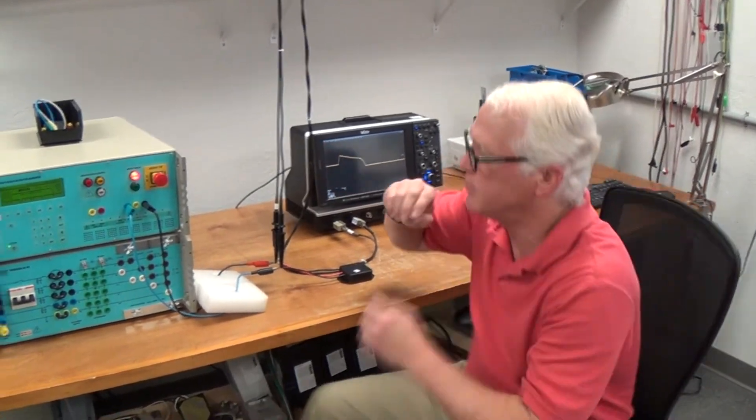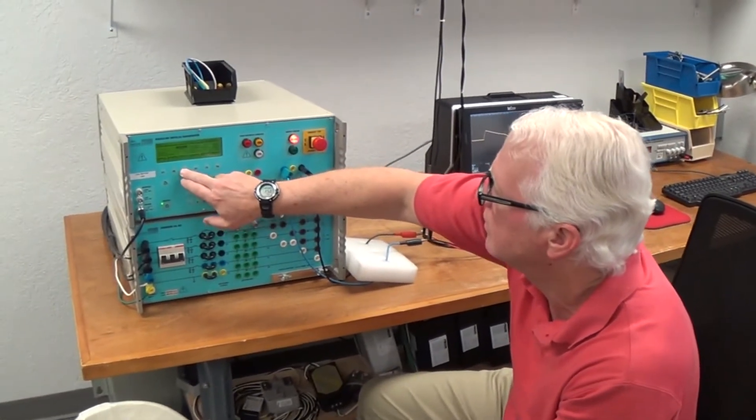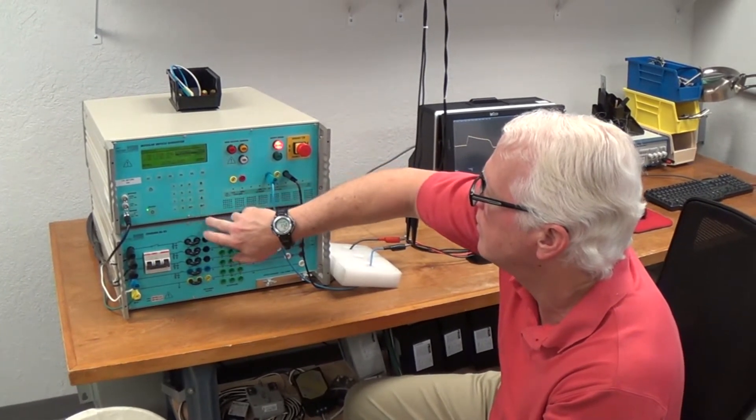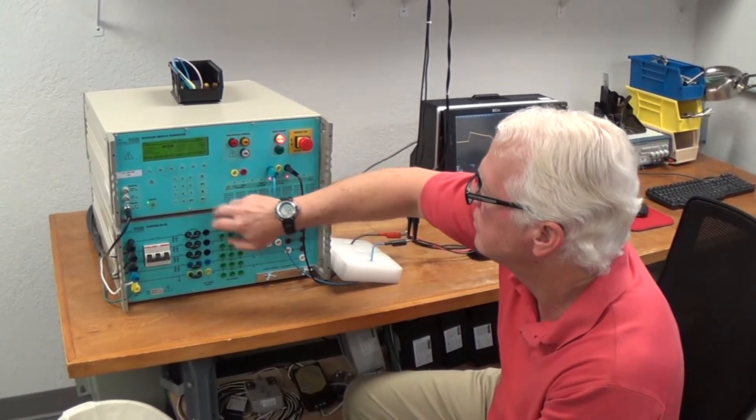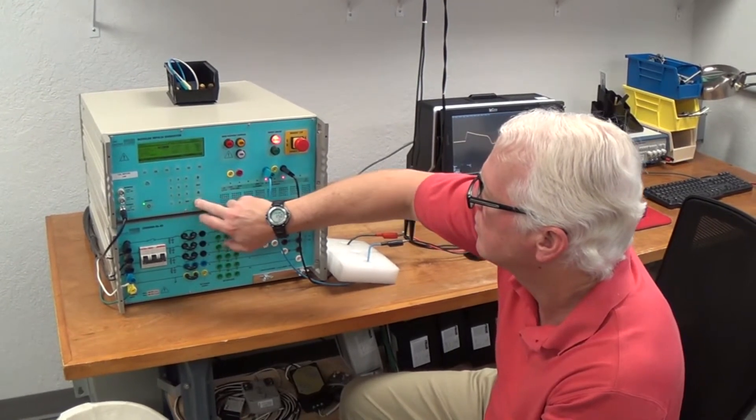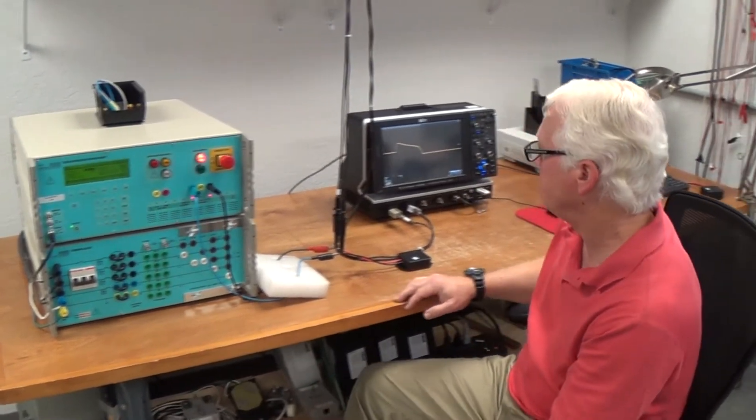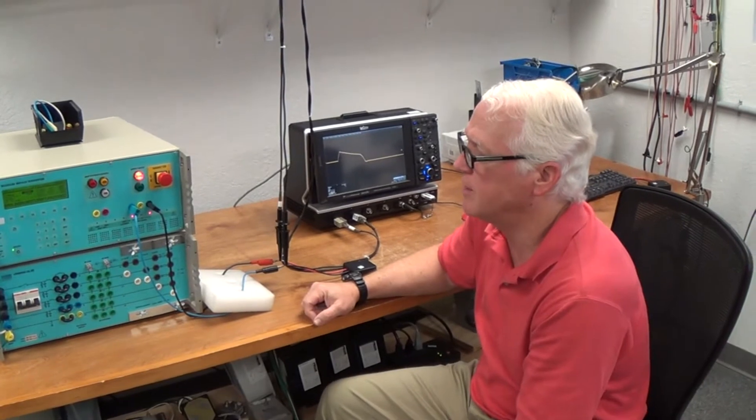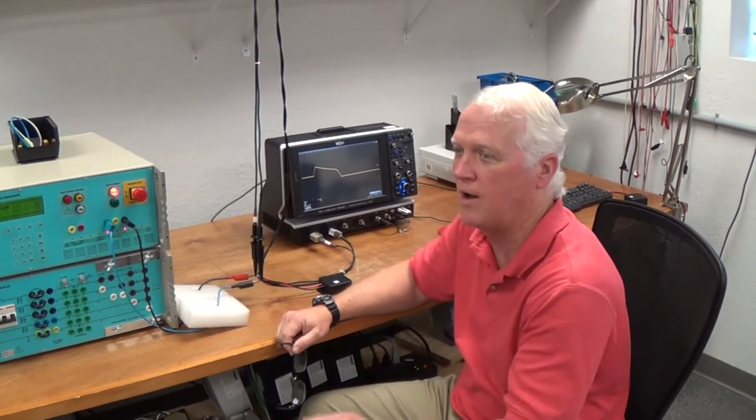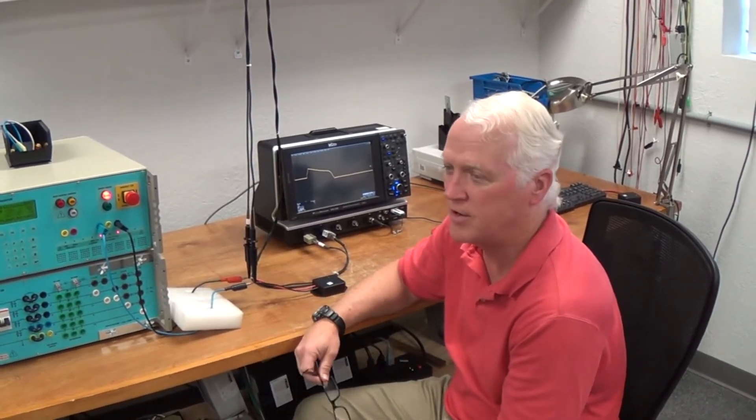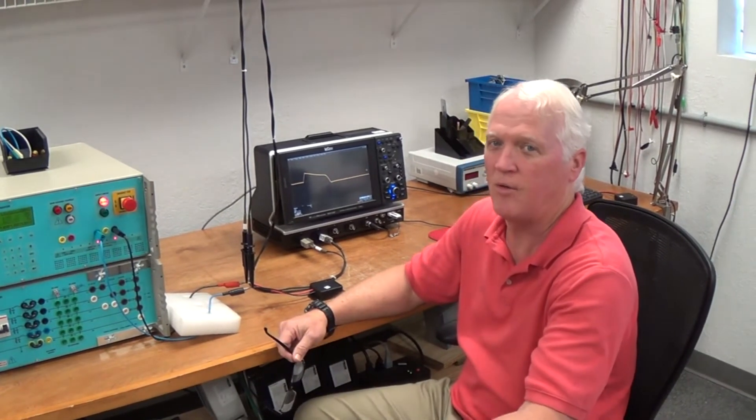So I'll change it now to a 2,000 volt ringing waveform. Okay, now let's say this simulates the internally generated transients, and you get a lot of them. A lot more internally generated transients because your electronics are always working.